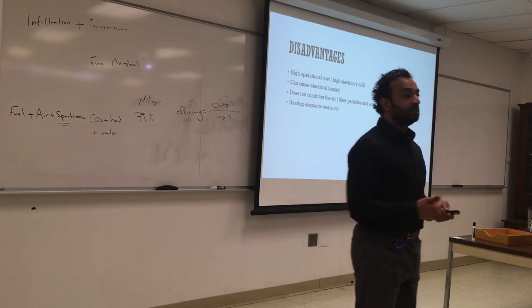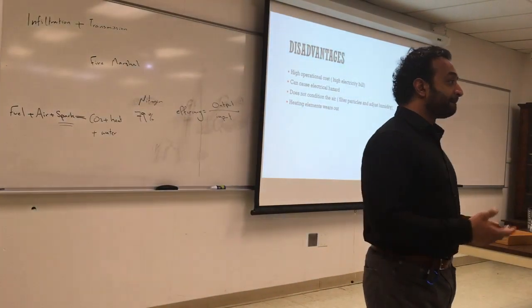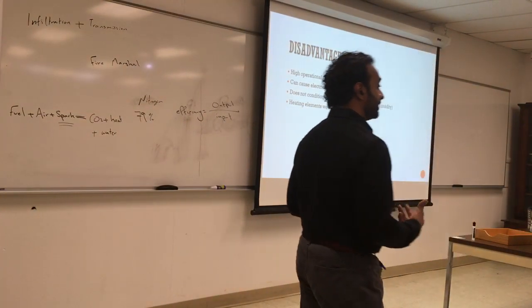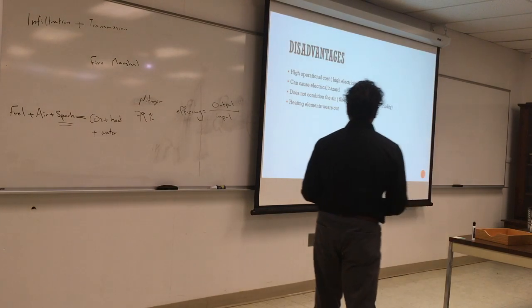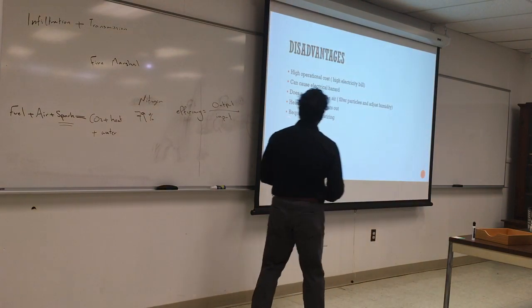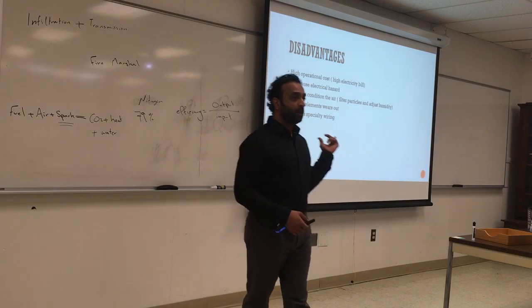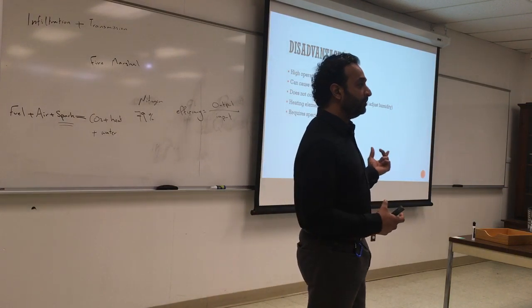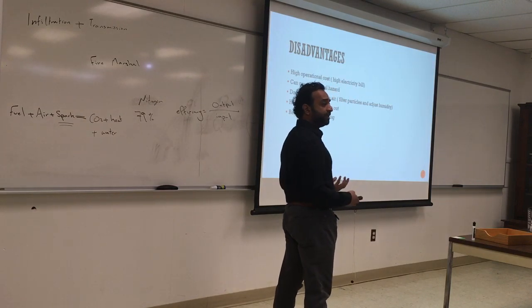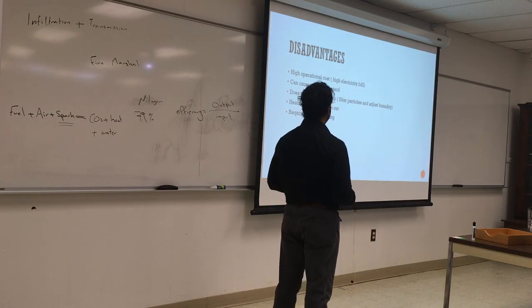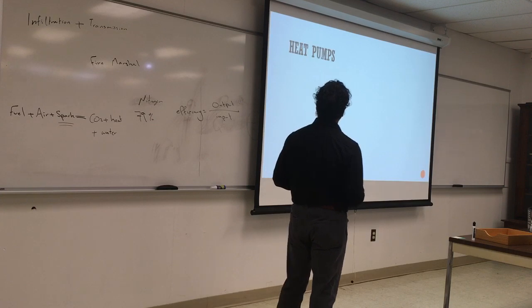It's not that expensive, but they do wear out after time. The resistance inside the coil changes over time because of the constant heating and unheating. So it has to be changed. They require specialty wiring. The wire has to be large enough to handle the amount of amperage that's being drawn. Otherwise, it will overheat and cause an electrical fire.